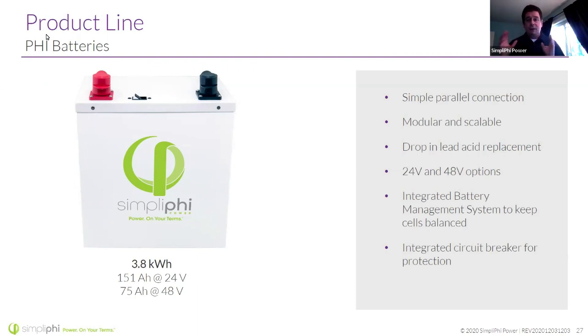These were originally designed as a great drop-in lead acid replacement. So you go out to one of those banks, like in the last slide, the batteries have reached end of life, and the customer's tired of maintaining them, or you're tired of having that maintenance contract. Sell them some SimpliPHI instead. It does have an integrated battery management system to keep the cells balanced and to provide those basic protections. And I should have said it earlier, those basic protections do not make up for a poorly designed system. They're more of a backstop for if something happens. And all of our products have a breaker. I love the breaker. It's a simple but brilliant safety measure where you can make sure that your system's de-energized at each battery if you need to do installation or maintenance or anything on them.